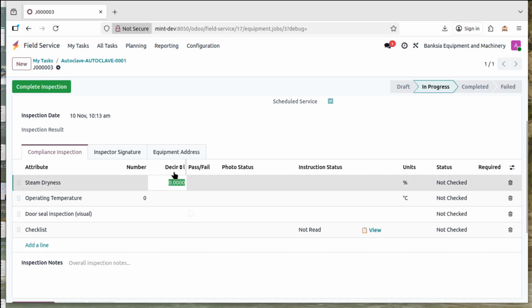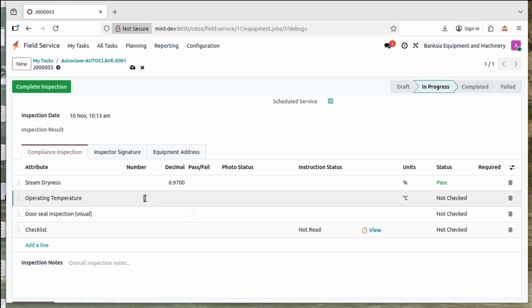If I put in, say, 0.97 for the dryness, I'd be measuring that with a meter inside the autoclave — I wouldn't just be guessing it. I can see that passes, so it's within tolerance. That's 97% dryness, or flipping it around, 3% humidity, which is a pass in this case.